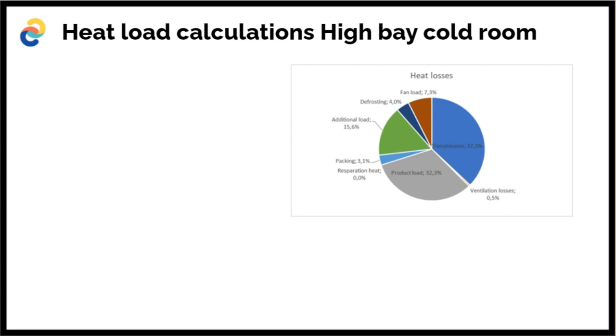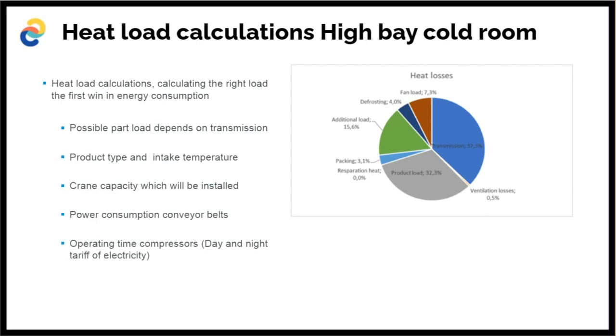And then, of course, the fan load, those are the big coolers. We're talking about big coolers here because one cooler could be approximately 300 to 400 kilowatts and give a lot of fan load. So what are we going to do with these heat loads then? First of all, we need to calculate the right load, but the right load is very, very subjective. So we have to look at part loads depending on transmission. Well, we're here in Southeast Asia and the climatic conditions are not changing that much. There's not much of a summer and winter condition in the Philippines.